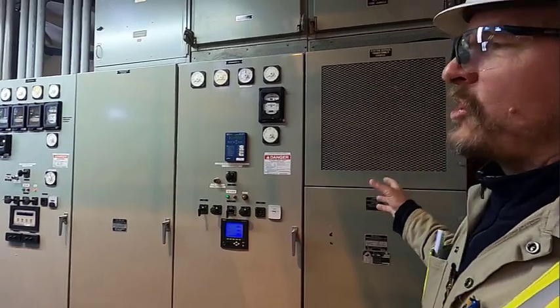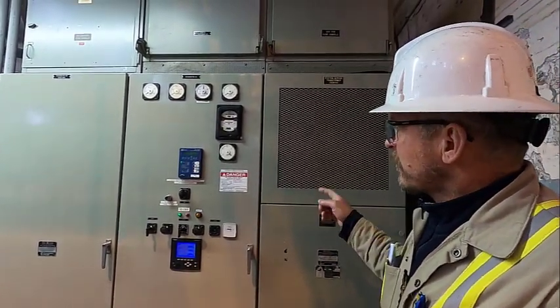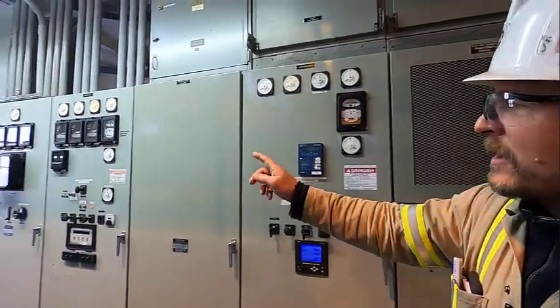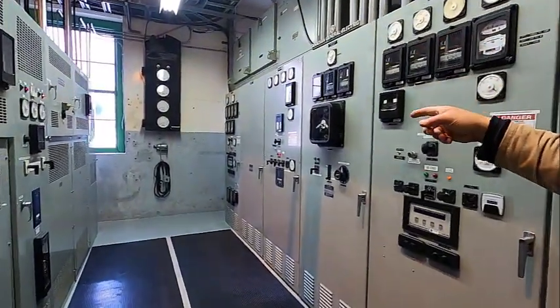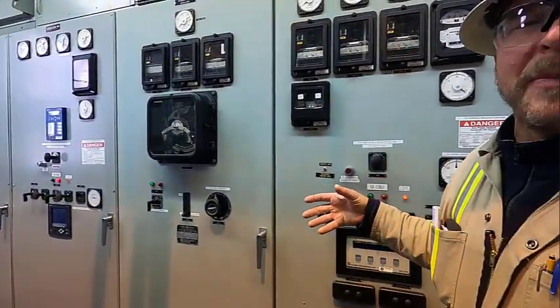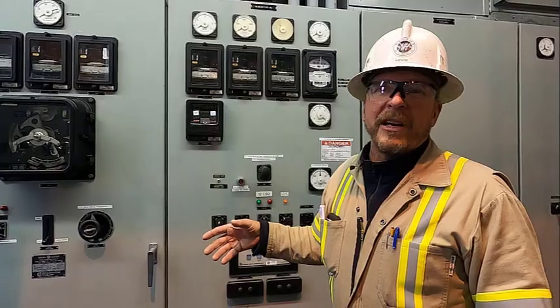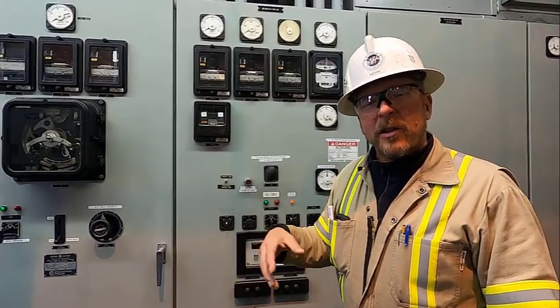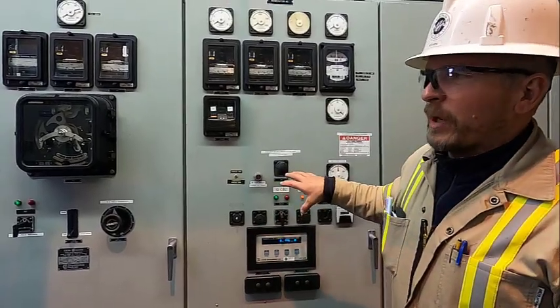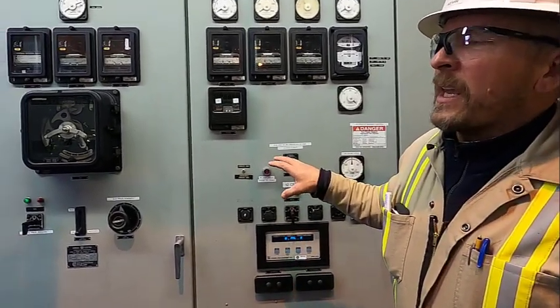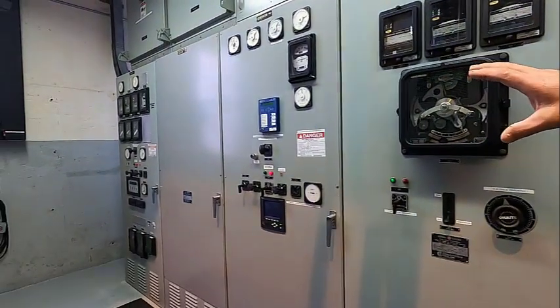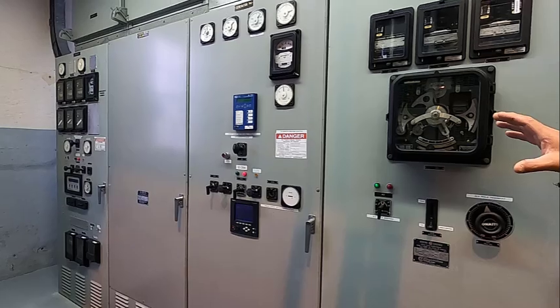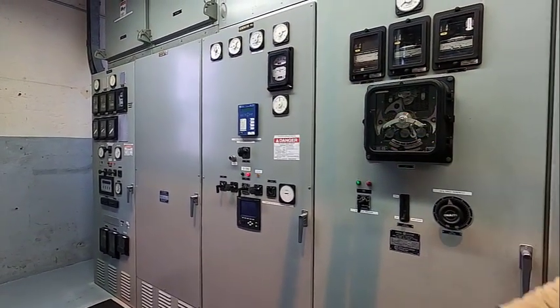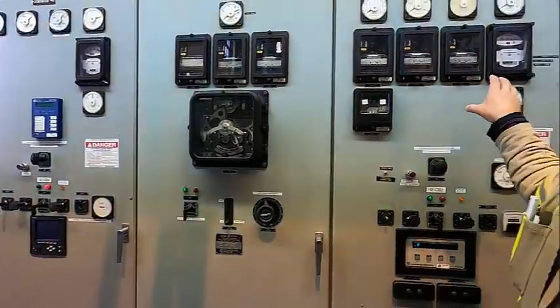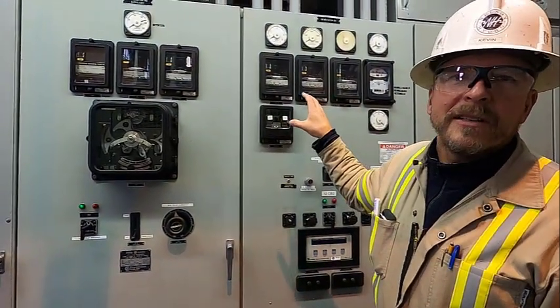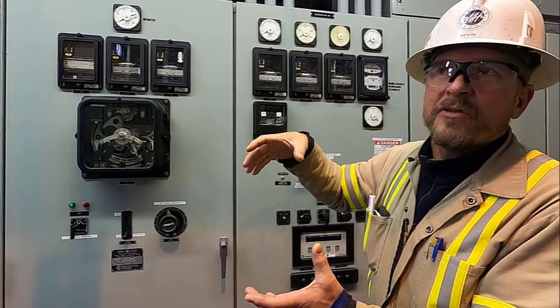Switchgear. Each generator has its own circuit breaker. So right here it's unit 3, unit 2, unit 4, and then we have a main circuit breaker. These circuit breakers are basically just a big electrical switch to separate the generator from the line or the load. These breakers inside of here are at 12,000 volts. And then the main is a kind of redundancy backup breaker that if there's a major fault here, the main opens to clear the fault behind. In behind all this, there's insulated copper conductor inside a real scoop of insulation for 12,000 volts.